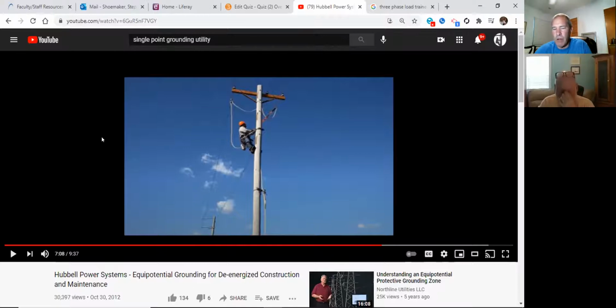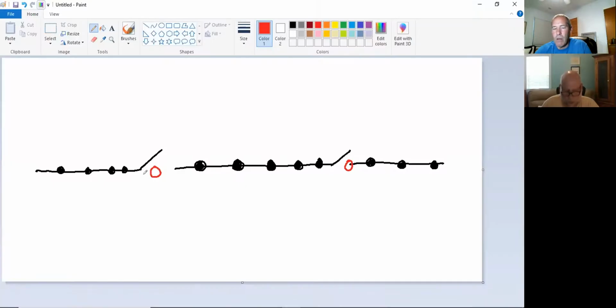Okay, so essentially, gentlemen, different companies are going to have different work practices. Our practice was that if you had to climb a pole or work in a bucket truck on a pole and you were doing the grounding process, you had to have single point grounding. Every location on a pole that you were working needed to have a ground set. Dual point grounding, and we'll get to the video in just a moment, is if I put a set of grounds at this first open point on this conductor, and then put a set of grounds at the other end of the part of the line where I have this open switch, anybody can work inside the zone and all of these poles would not need to be grounded. Santee Cooper's rule is every time you went to each individual structure, you had to have a set of grounds. That's single point grounding.